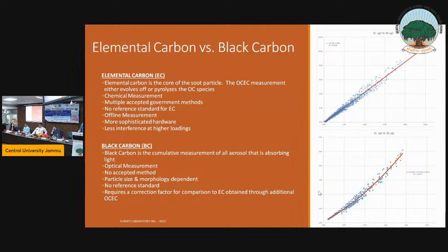Then you wouldn't really worry about it, because we also have algorithms. You can actually see the laser change as it gets hotter. Remember that OCEC instruments cool down, and when they cool down, you see the inverse of these metals cooling and interacting with the laser. So you can use some fancy math and determine those effects on the filter as it's heating.